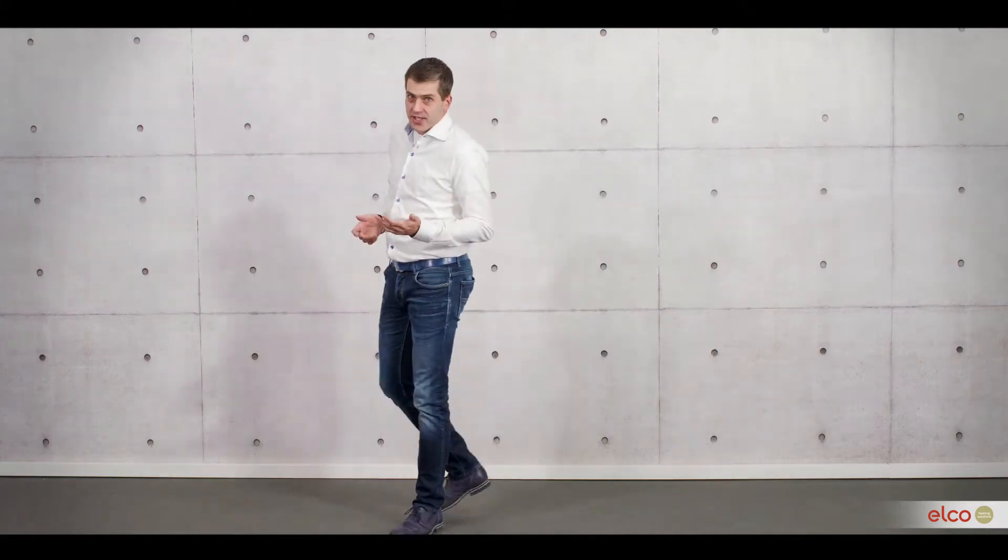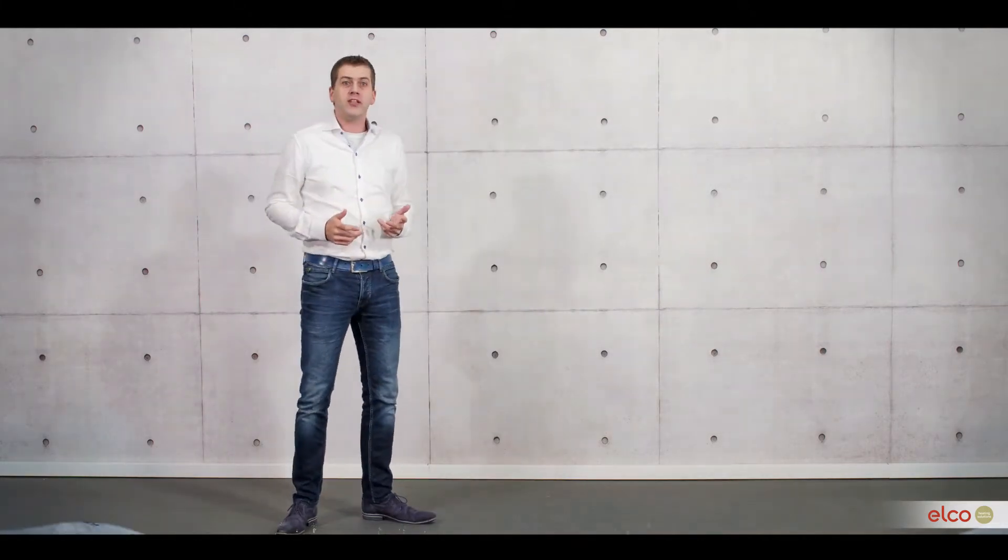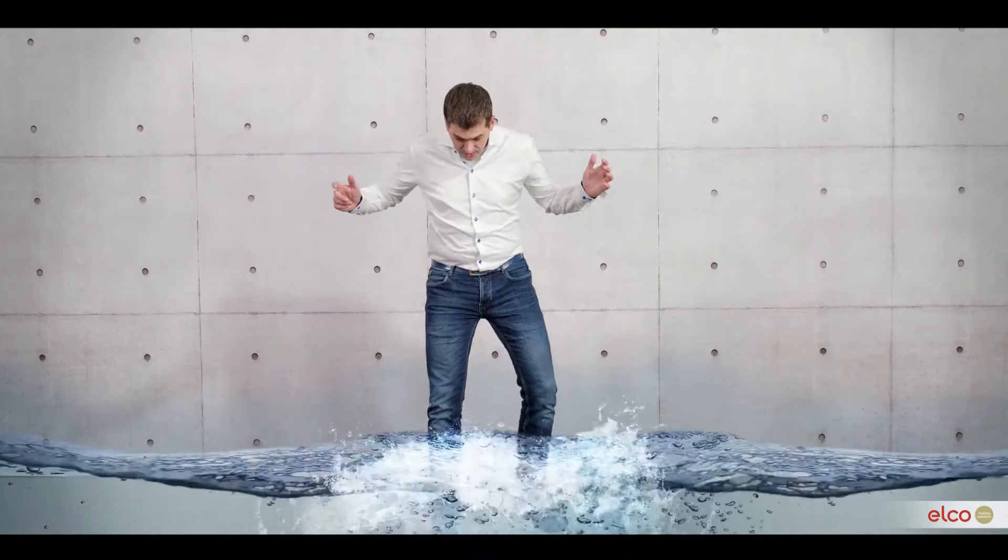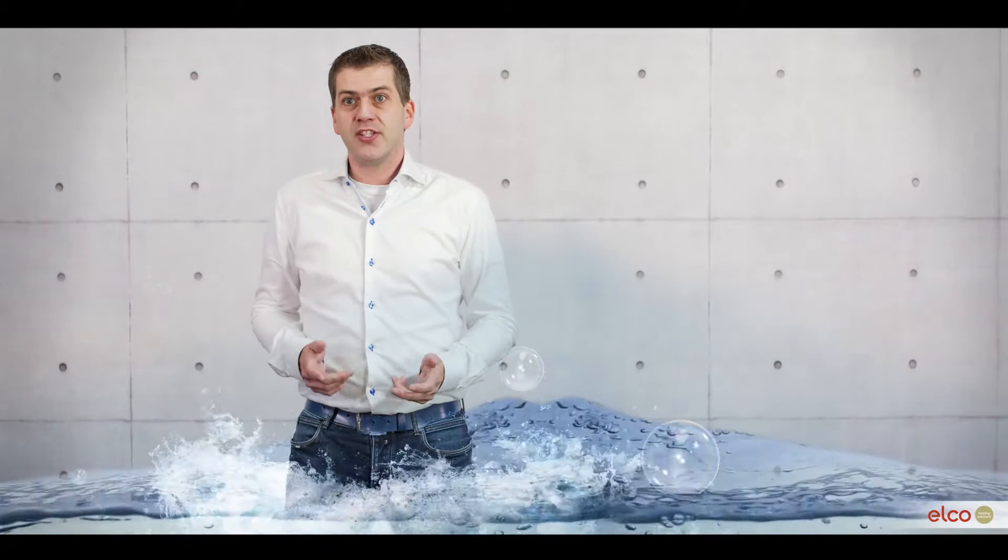Let's first take a look at the water side of the heat exchanger. A stainless steel heat exchanger is hardly affected by the water quality in the heating system. Whoa! Okay, it can work with a wider pH range than heat exchangers made from other materials. Plus, higher chloride levels are not a problem.